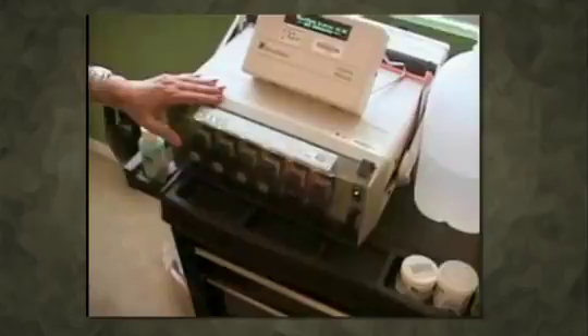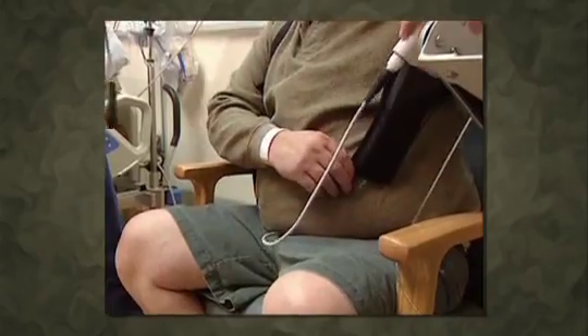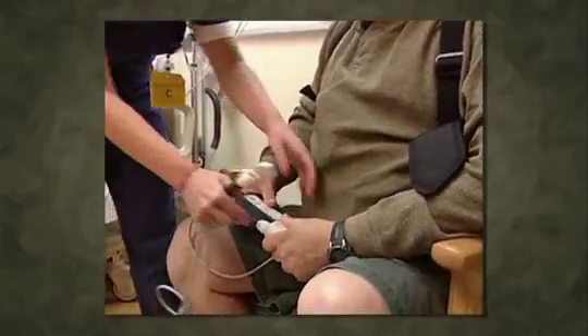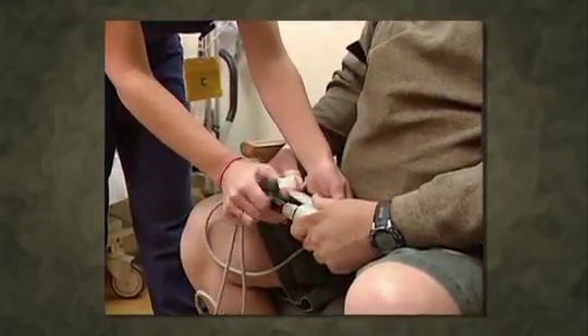It is also important to note that the patient must be connected to a power source at all times, whether it's the power module, batteries, or the emergency power pack. If necessary, the patient or their caregiver may transfer the system controller from one power source to the other.